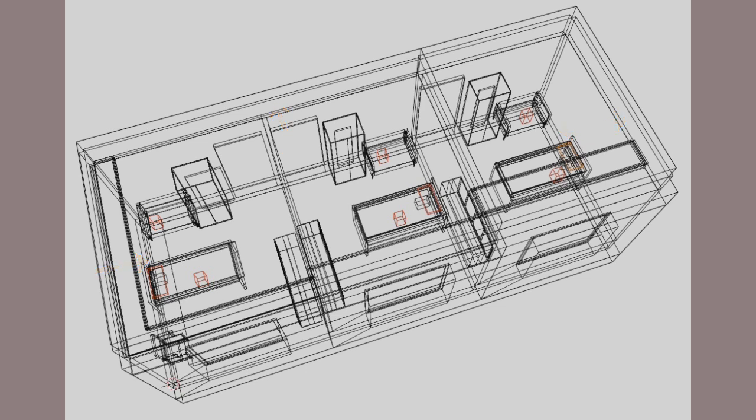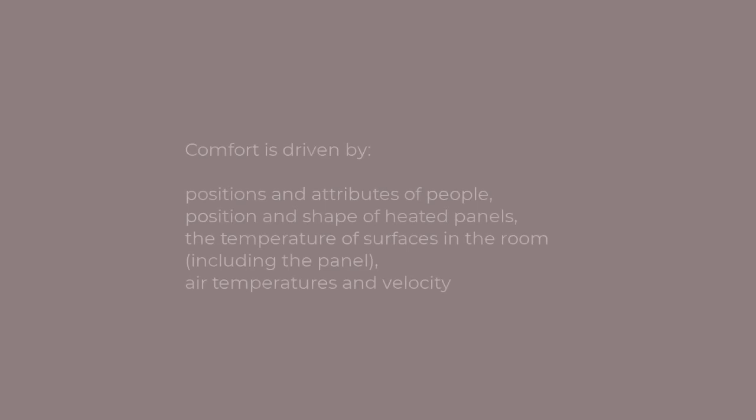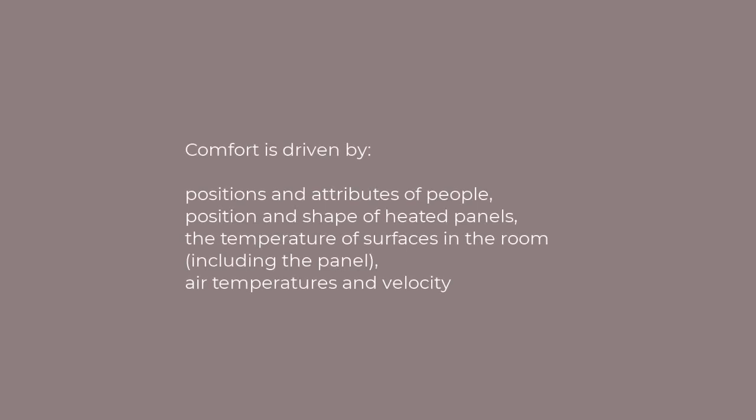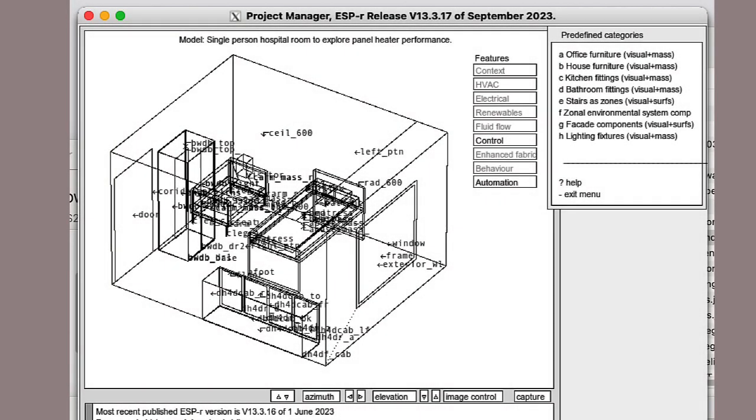I decided there was good reason to include furniture and fittings. First, their mass might actually alter the response characteristics of the room. And comfort's related to what's warm nearby. And therefore, if the panels actually warmed other surfaces in the room that were close to the occupant, that might alter the comfort perceptions. Is this over the top? Well, not really.